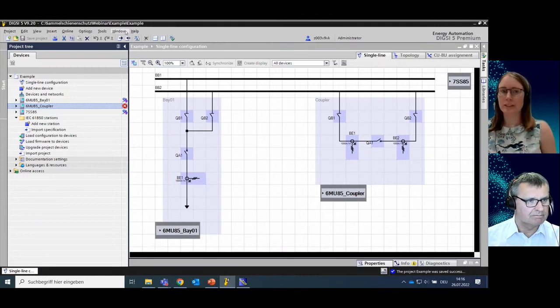I already prepared a new project in DIGSI. Here you can see nearly the same configuration as shown in the slide, but of course the missing parts we want to configure together. I already prepared one bay — this is the typical bay in our case and serves also as a copy master later on. I also prepared a single line of the coupler bay with the two CTs. The two merging units are already configured and the 7SS85 is also already created in this project. In the next step we want to complete the configuration of the first merging unit of the first bay, then copy the first bay to create the second bay, check all configuration settings, and finally do the process bus mapping and communication mapping.